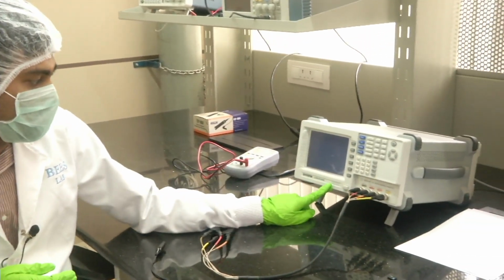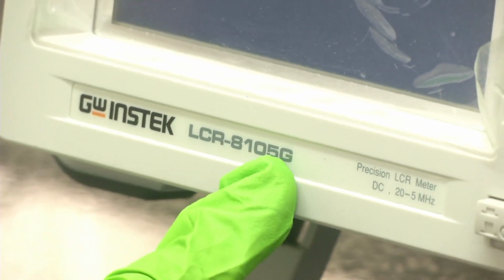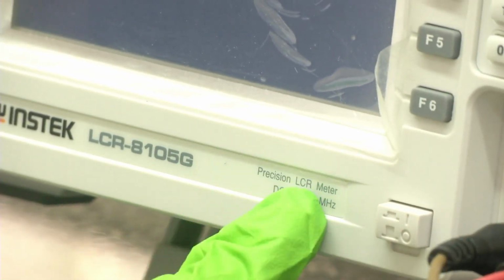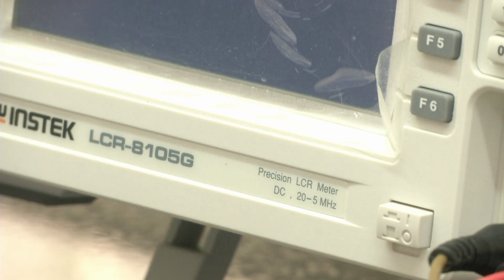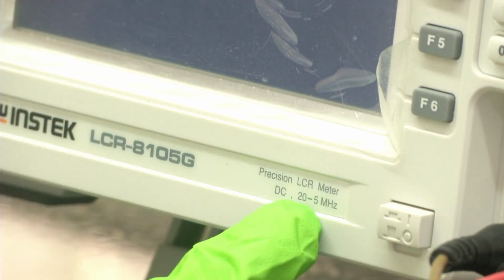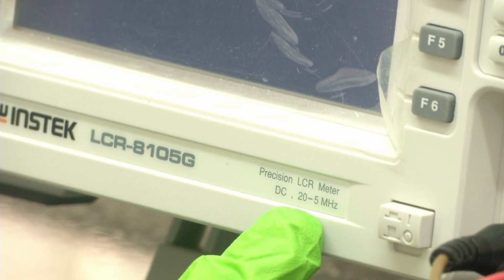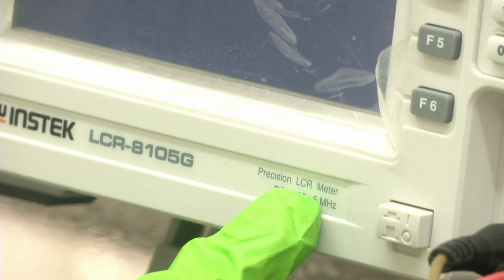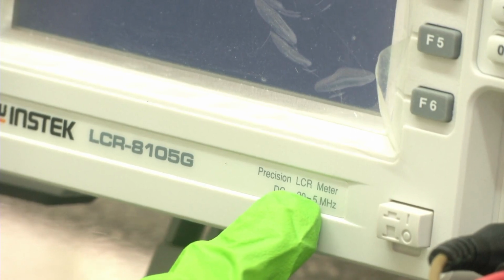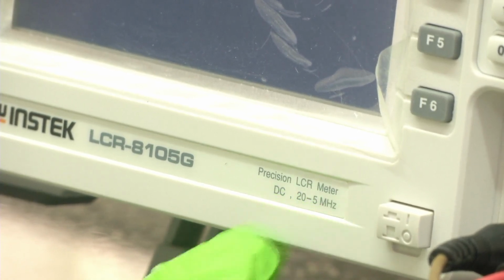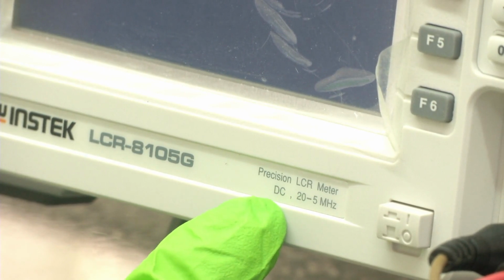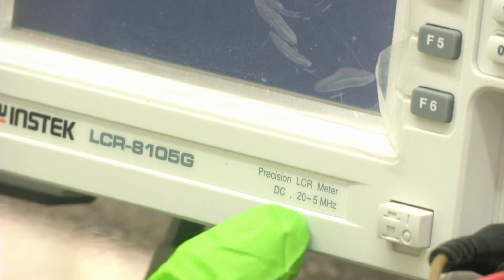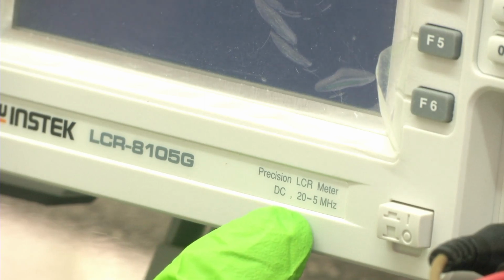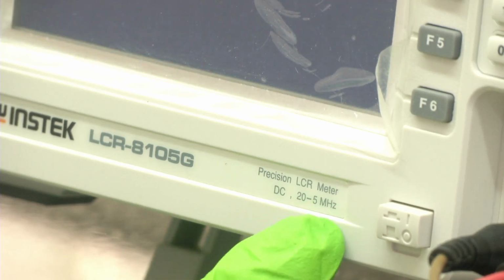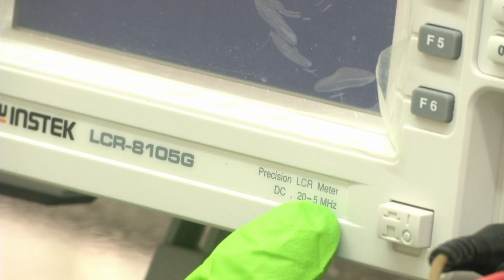If you can see here in the description, this is a GW Instek LCR-8105G equipment. This is basically an impedance analyzer, or we can call it an LCR meter. By LCR, yes, you guessed it correctly: L is inductance, C is capacitor, R is resistance. So it is measuring different impedance related quantities like capacitance, total impedance, inductance and all, and it can measure DC resistance, and also the total impedance, inductance and capacitance from 20 hertz up to 5 megahertz. That is the specialty of this equipment.